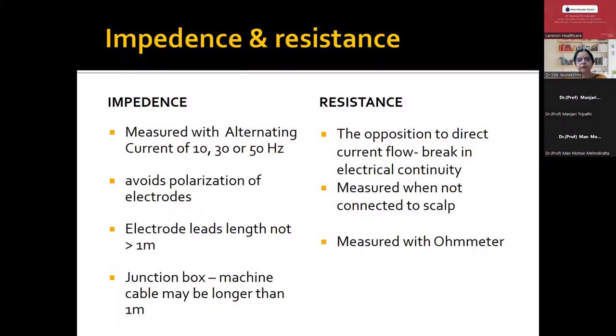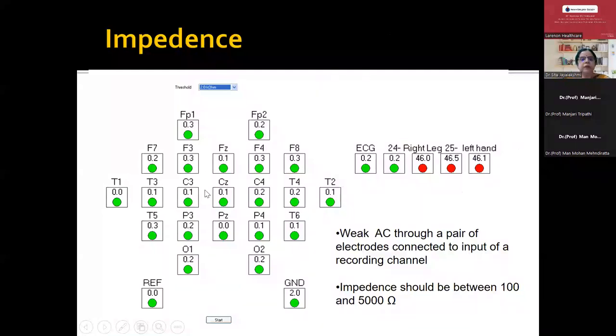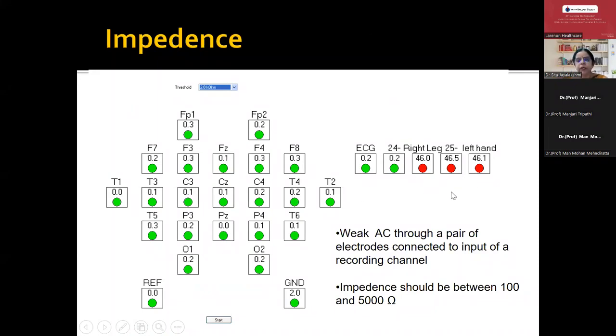We should know what is impedance and resistance of the machine. Both may sound synonymous, but impedance is measured using alternating current, whereas resistance is the opposition to direct current flow. Normally we measure impedance once we connect all the electrodes. The machine automatically gives you the impedance — whatever shows in green, the impedance is good; if something is in red, the impedance is poor. You then clean that area, check for dirt or sweat, and adjust it. Impedance should be between 100 to 5000 ohms.